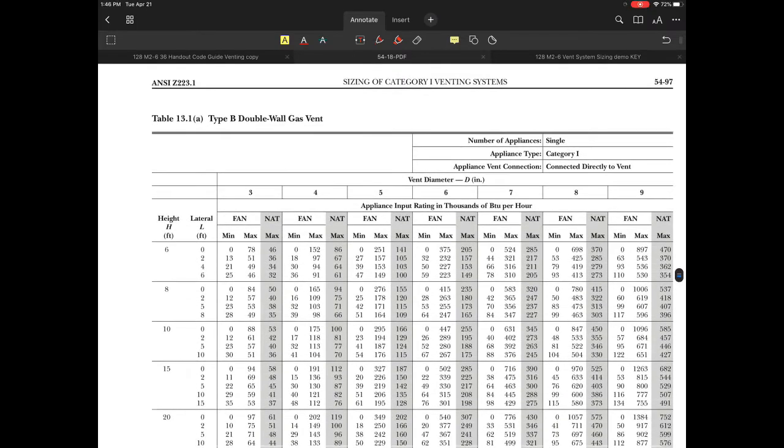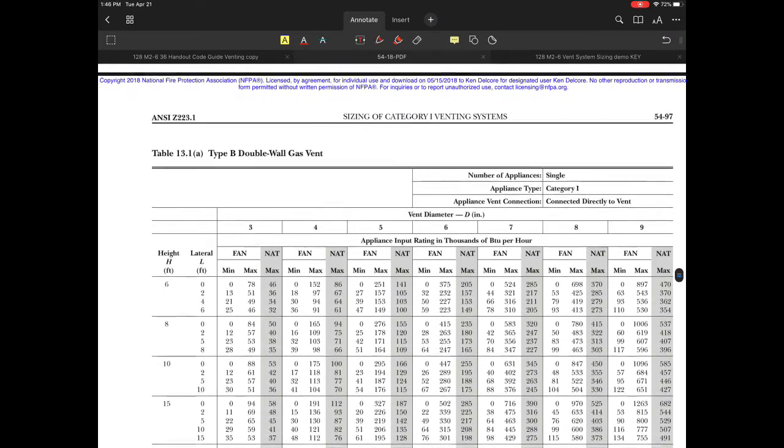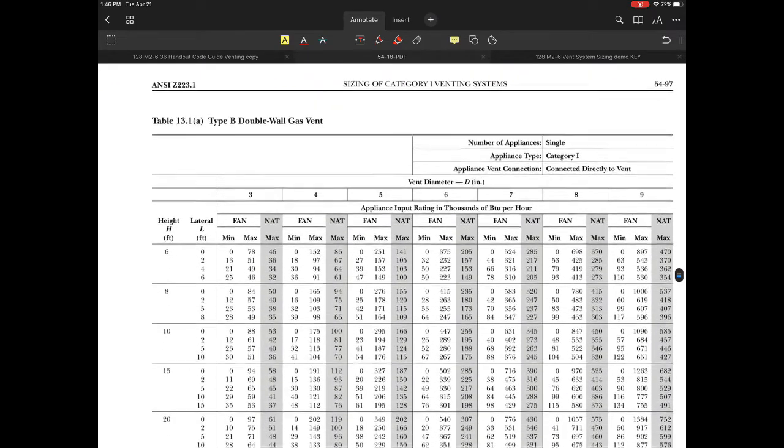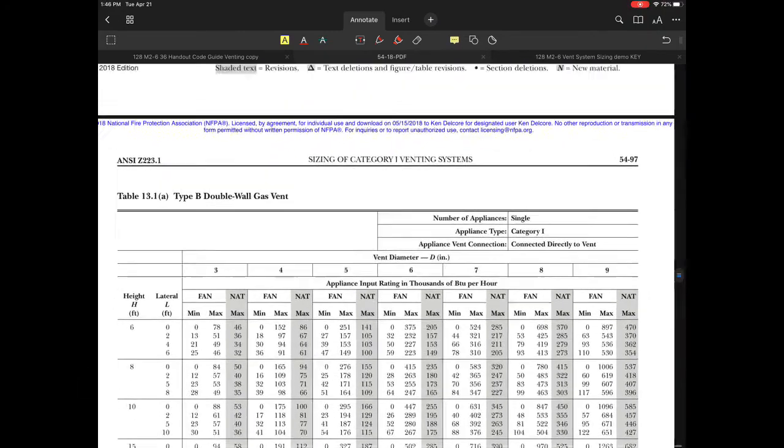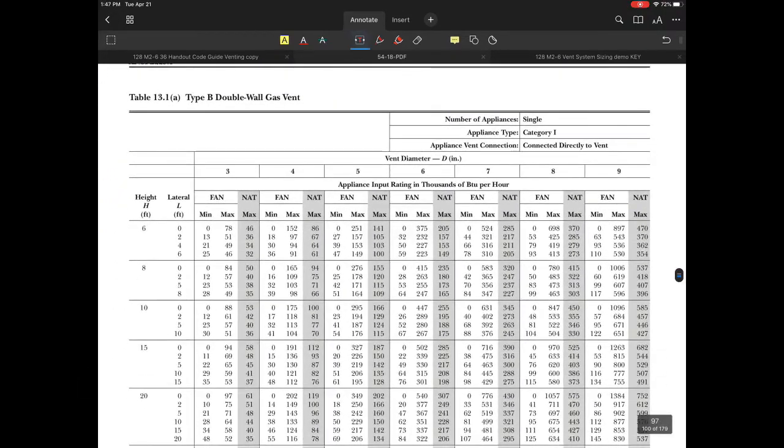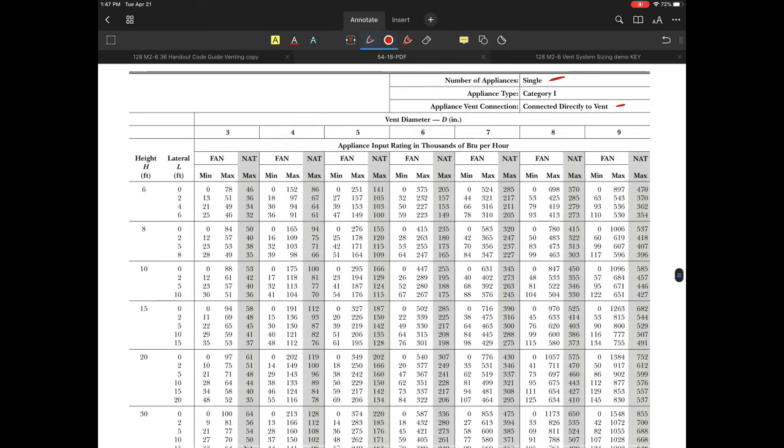Looking in the 2018 National Fuel Gas Code book, I'm using table 13.1A for a single category one appliance connected directly to the vent. The B vent goes right to the appliance. Notice the vent heights and laterals in the table.